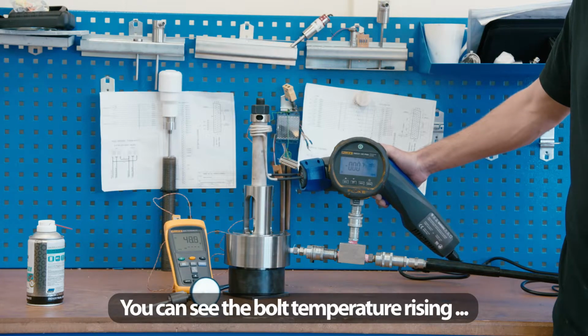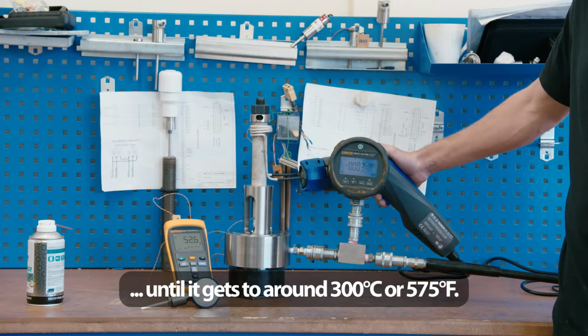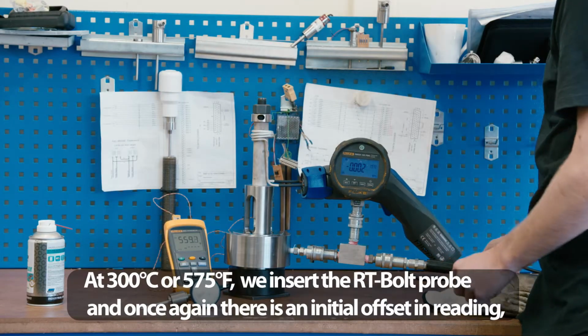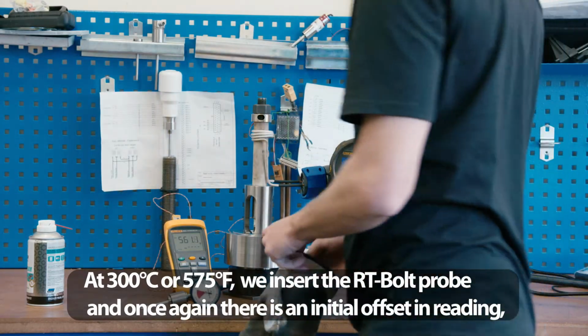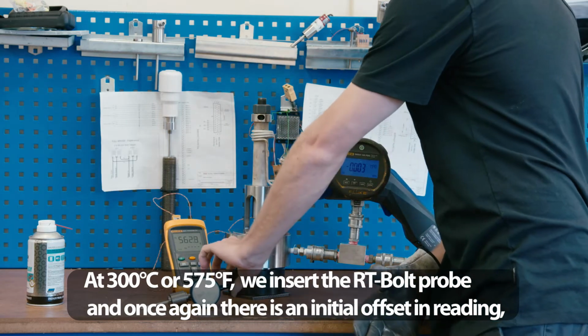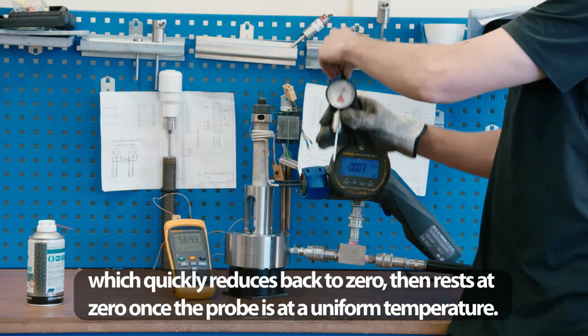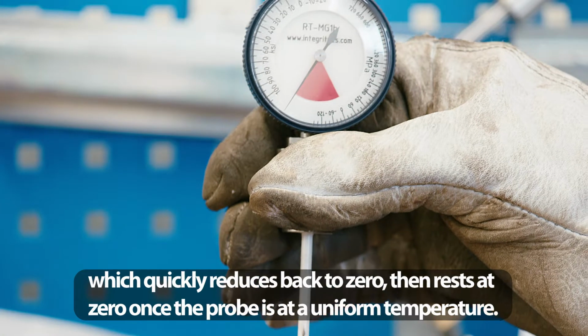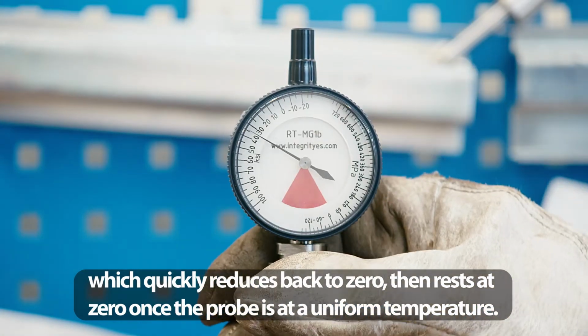And you can see the bolt temperature rising until it gets to around 300 degrees Celsius or 575 degrees Fahrenheit. Now the bolt is at a fairly high temperature. We insert the RT bolt probe, and once again there is an initial offset in reading, which quickly reduces back to 0, then rests at 0 once the probe is at a uniform temperature.